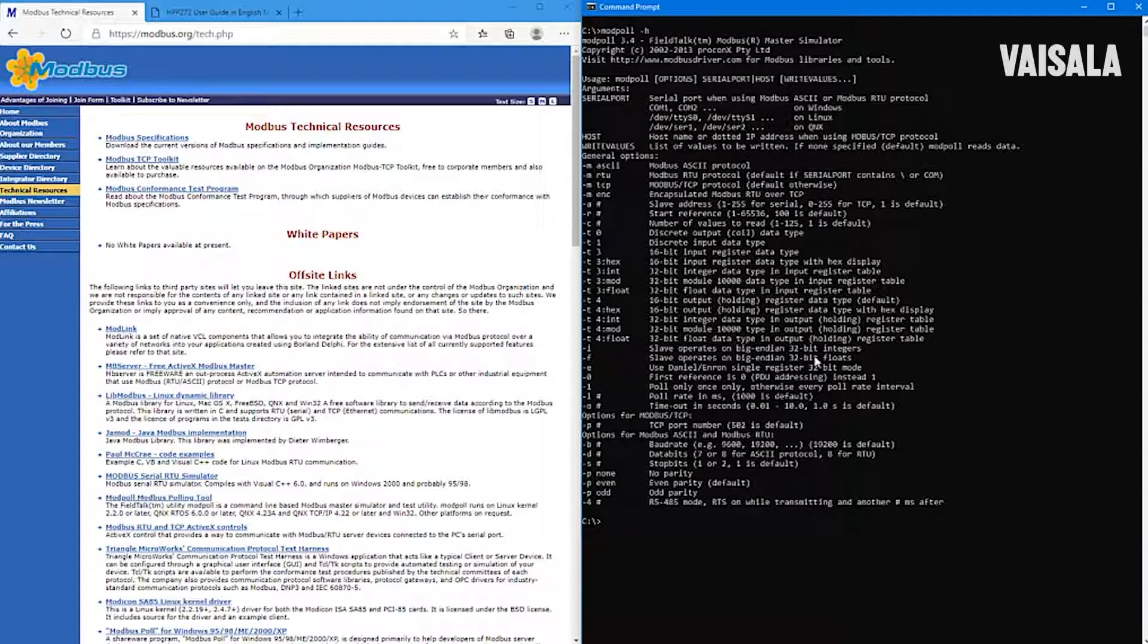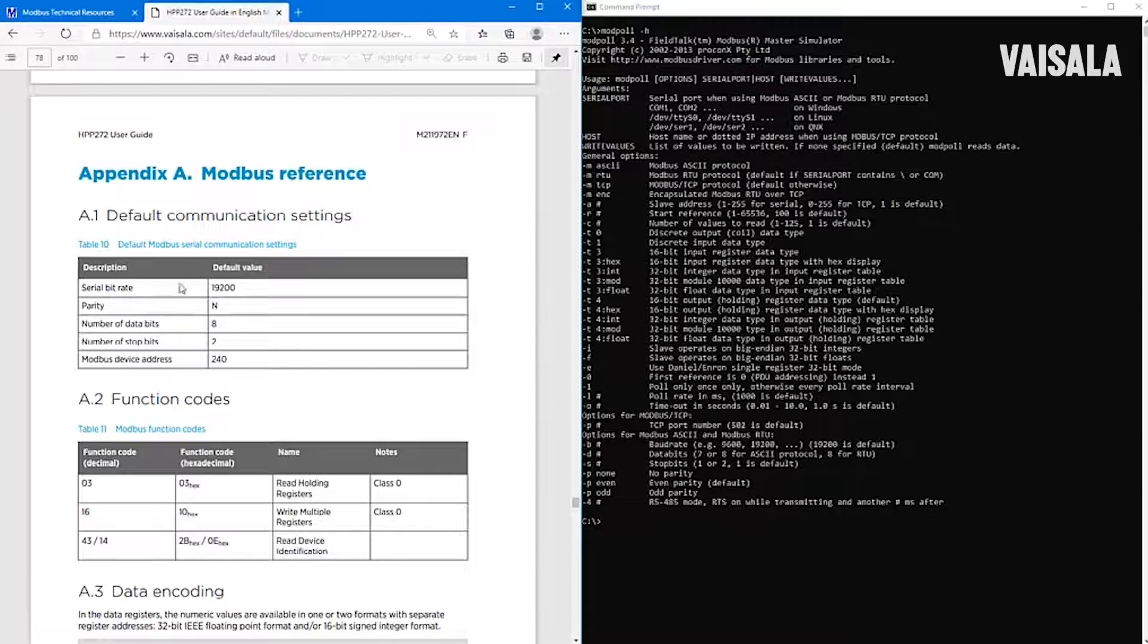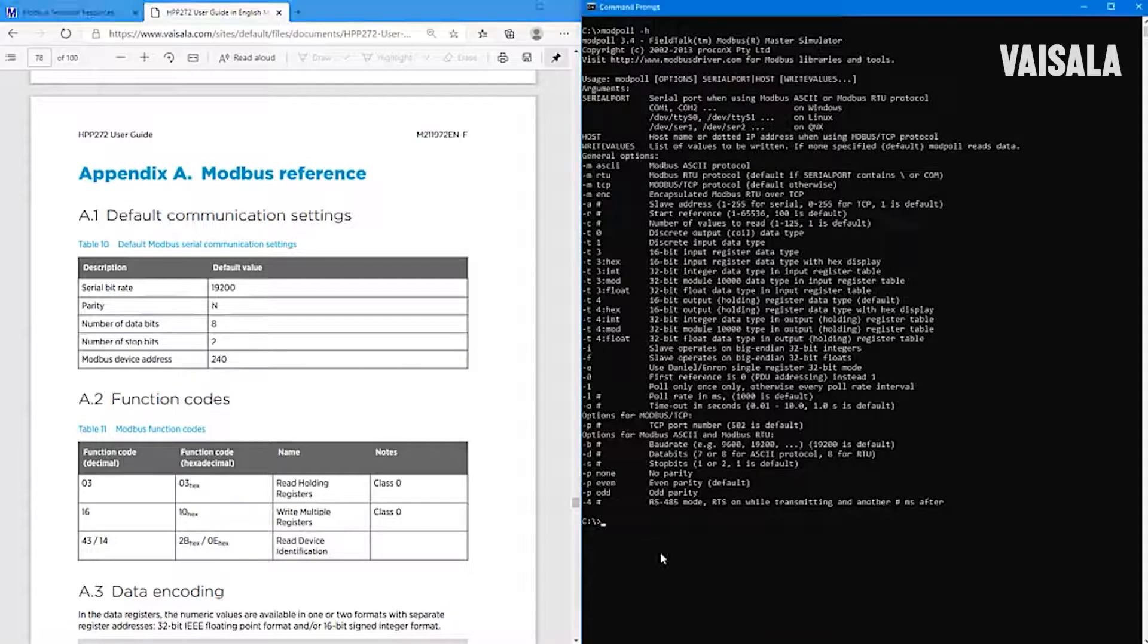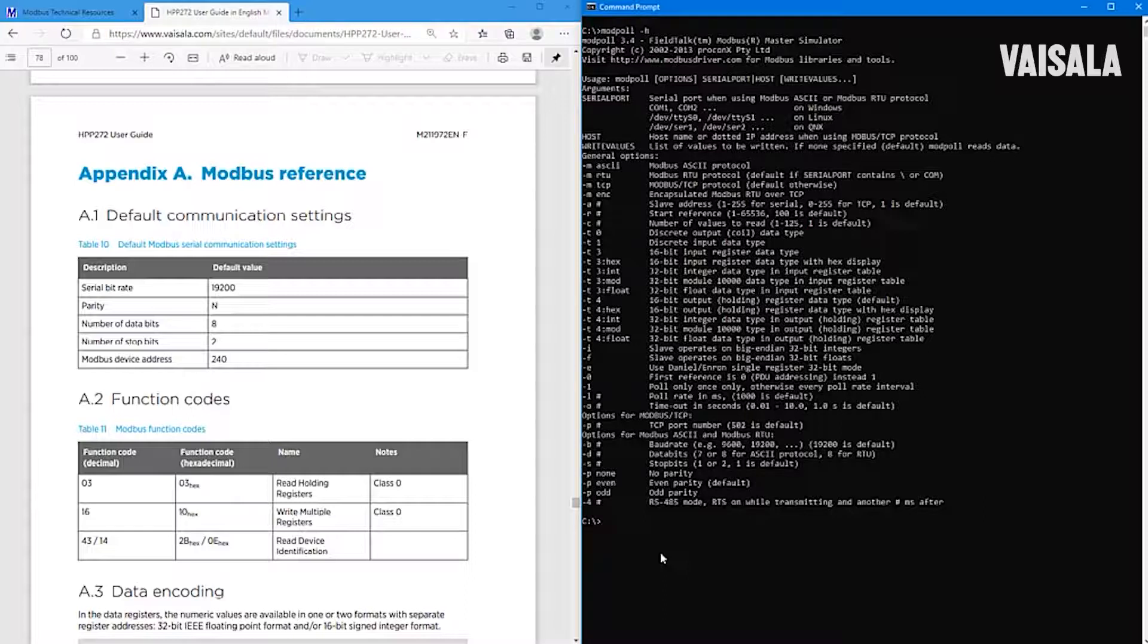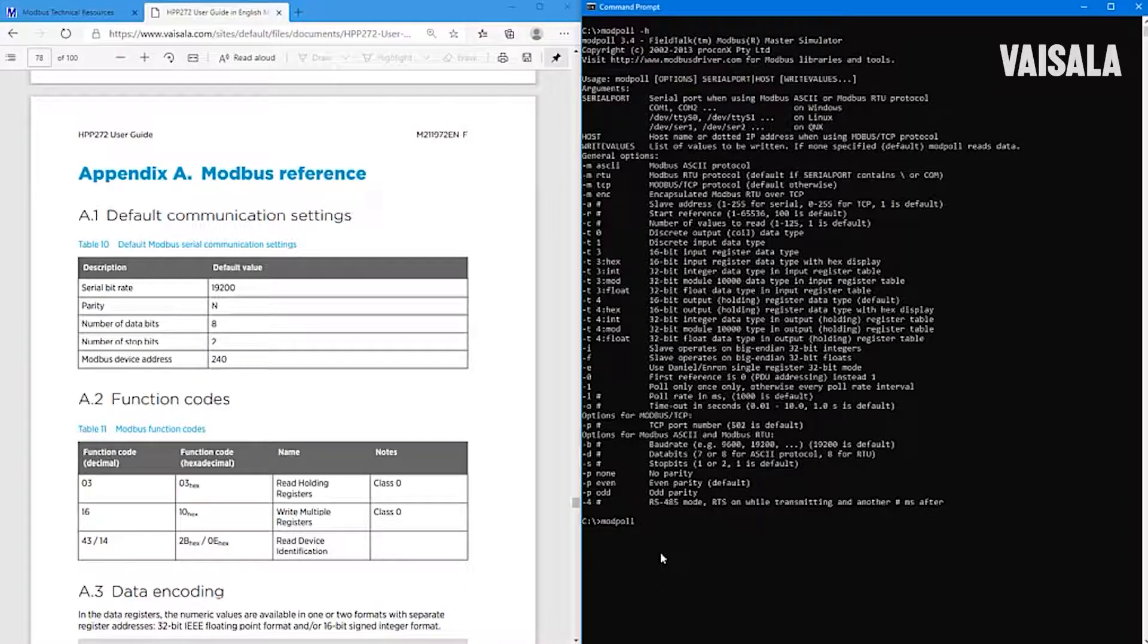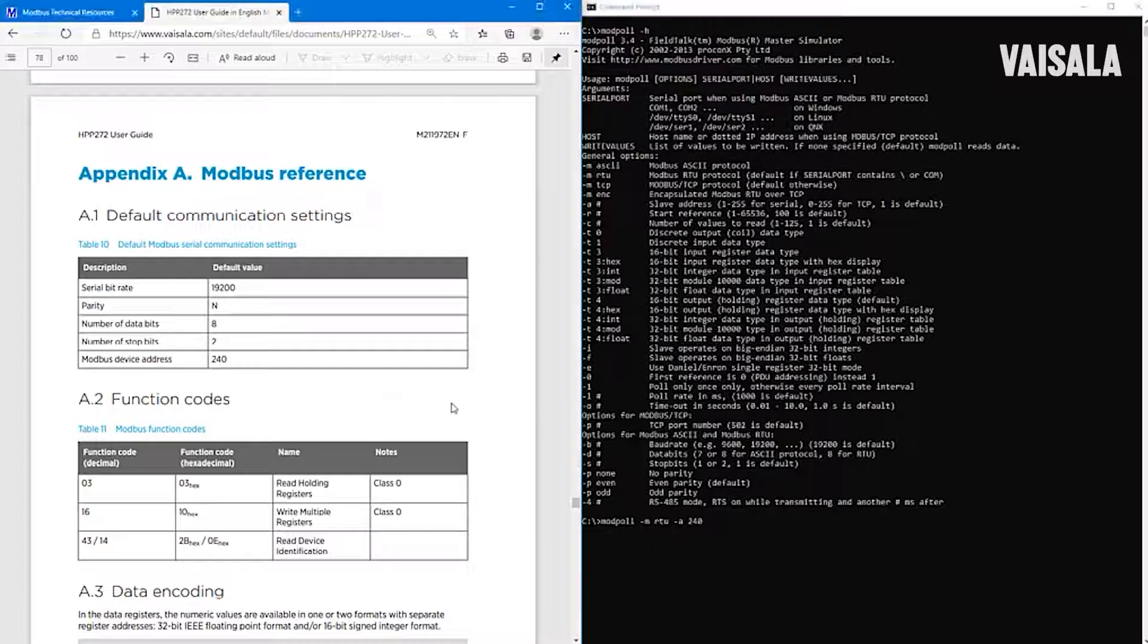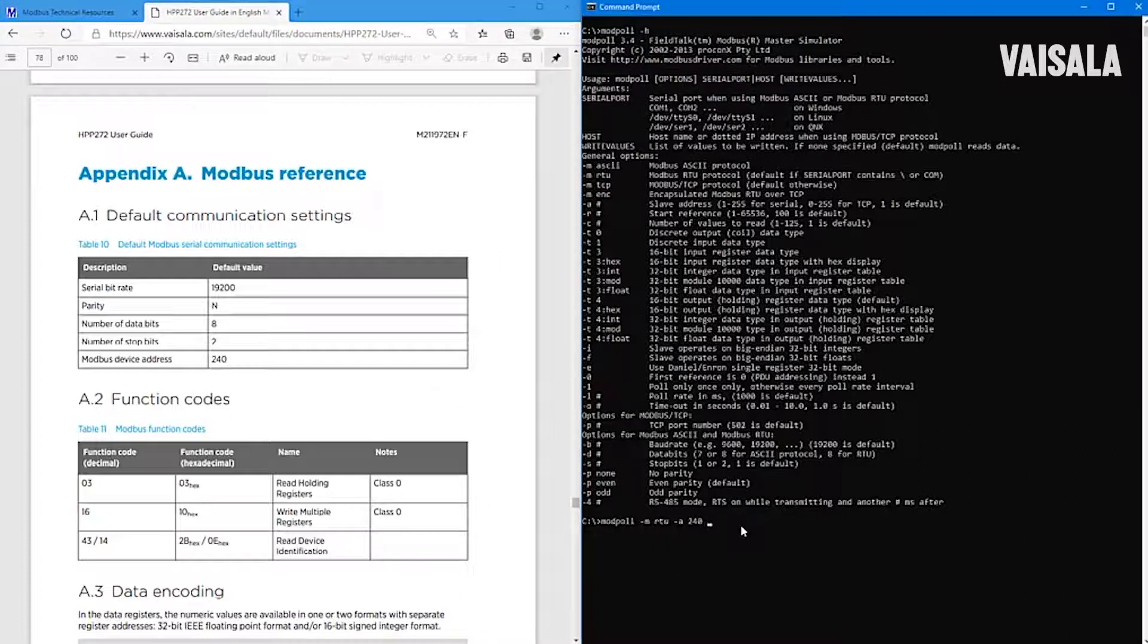So now I need to open the manual. First, I need to set the communication so that the communication settings are the same. This command starts with Modpoll, and then I will use RTU protocol here. And the default address is 240. And then I need to also adjust this parity.